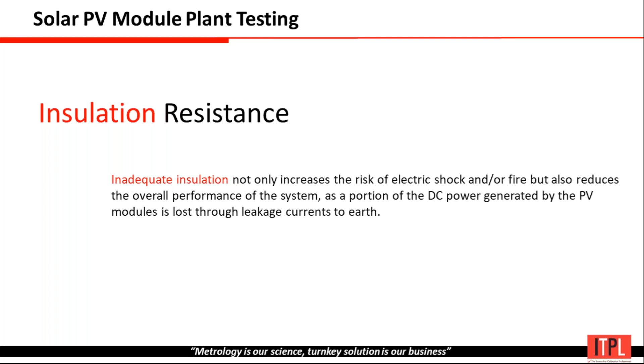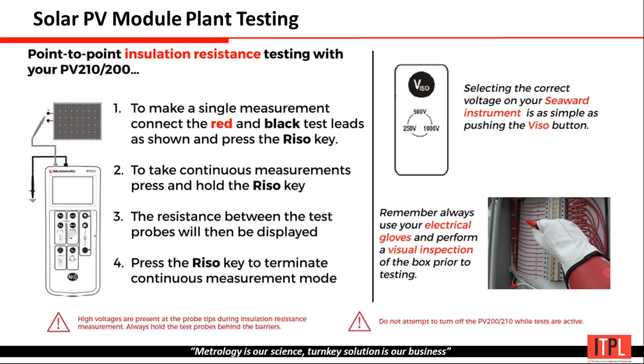If you want to test the insulation level between the cables, you can test that, or if you want to test the insulation level between the positive and negative of your solar panel cable and the earth, you can do that too. This is maximum up to 1 kV insulation level. Up to a maximum of 1 kV system voltage, you can test insulation resistance. We have to test that in plant testing.